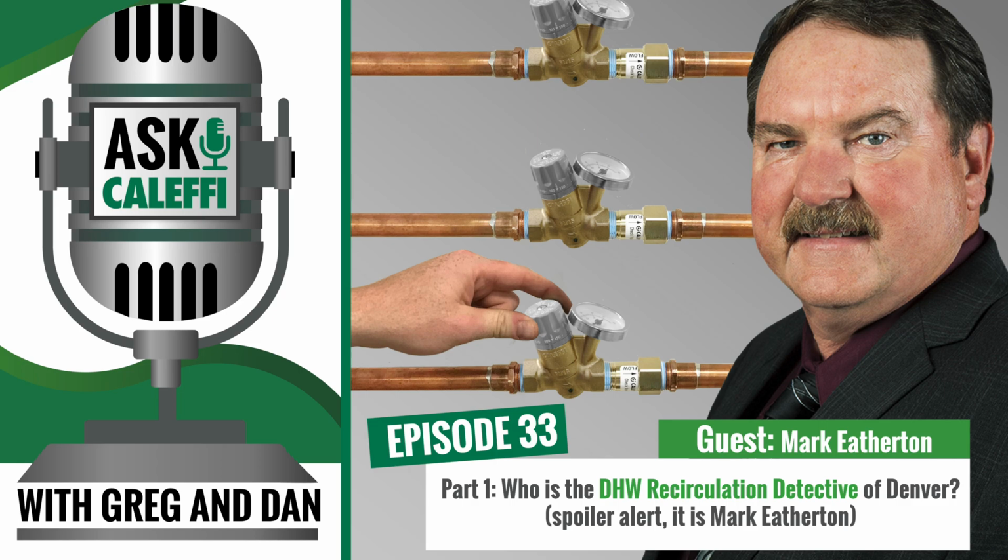But yeah, there's not too much information that you can gather. And the more information you have, the more accurate you're going to be in making recommendations. I mean, we don't only recommend the use of the Series 116, we also use the quick flow setters. If you've got a split in the branch of the hot water supply main, then you're going to have a split in the branches coming back. Then you want to make sure that you keep the water velocity within that pipe below an erosive velocity. And the only way that you can do that is to see literally what the gallons per minute movement is.